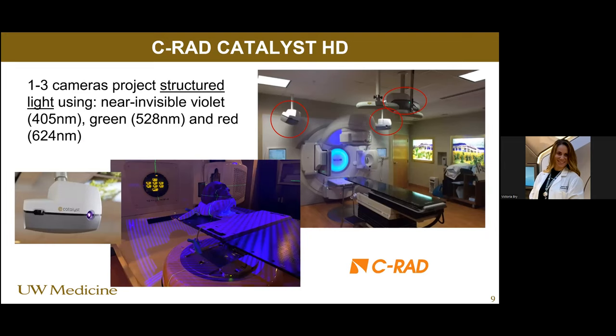Here is the C-RAD Catalyst HD system, from my old clinic in San Antonio, Texas. The C-RAD system uses typically one to three cameras and projects structured light — specifically a near-invisible violet light. You can see it projected onto a phantom on the table as lines. On the left is what the scanner looks like, and on the right you can see three of those scanners mounted on the ceiling above the treatment table.